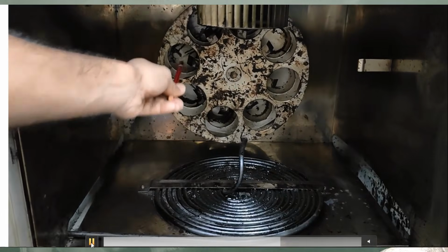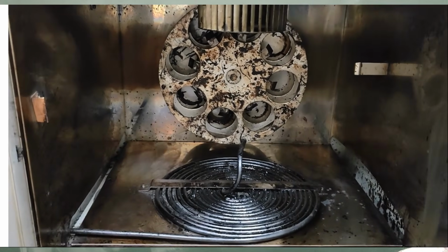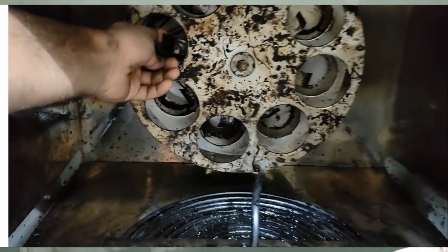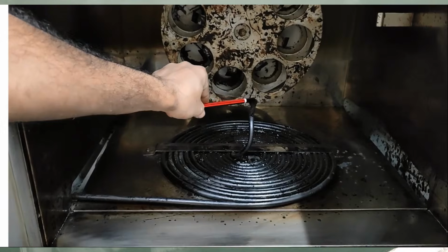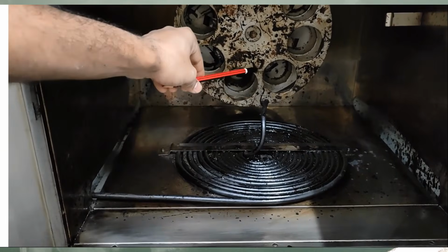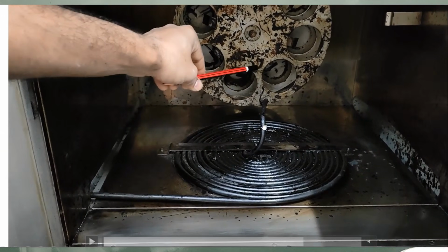You have a vertical carriage here, and this carriage can hold through clips firmly 8 glass containers in horizontal position. Here is an air jet to blow heated air into each bottle at its lowest point of travel, and the airflow is of the order of 4000 ml per minute, and it can be controlled by a flow meter.